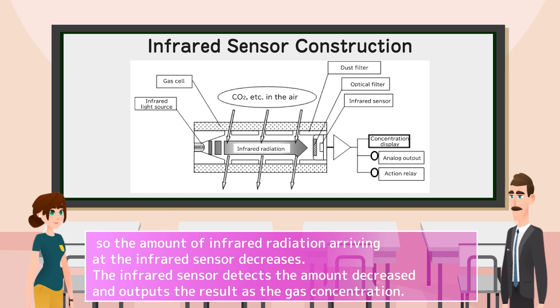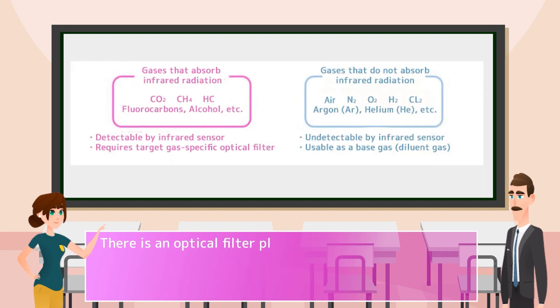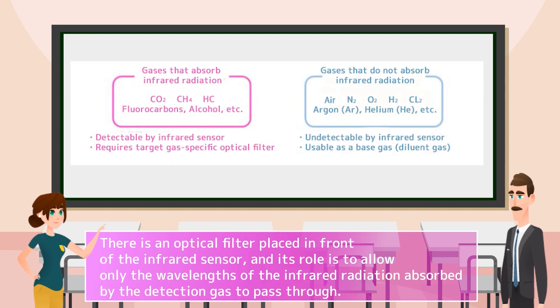The infrared sensor detects the amount decreased and outputs the result as the gas concentration. There is an optical filter placed in front of the infrared sensor, and its role is to allow only the wavelengths of the infrared radiation absorbed by the detection gas to pass through.